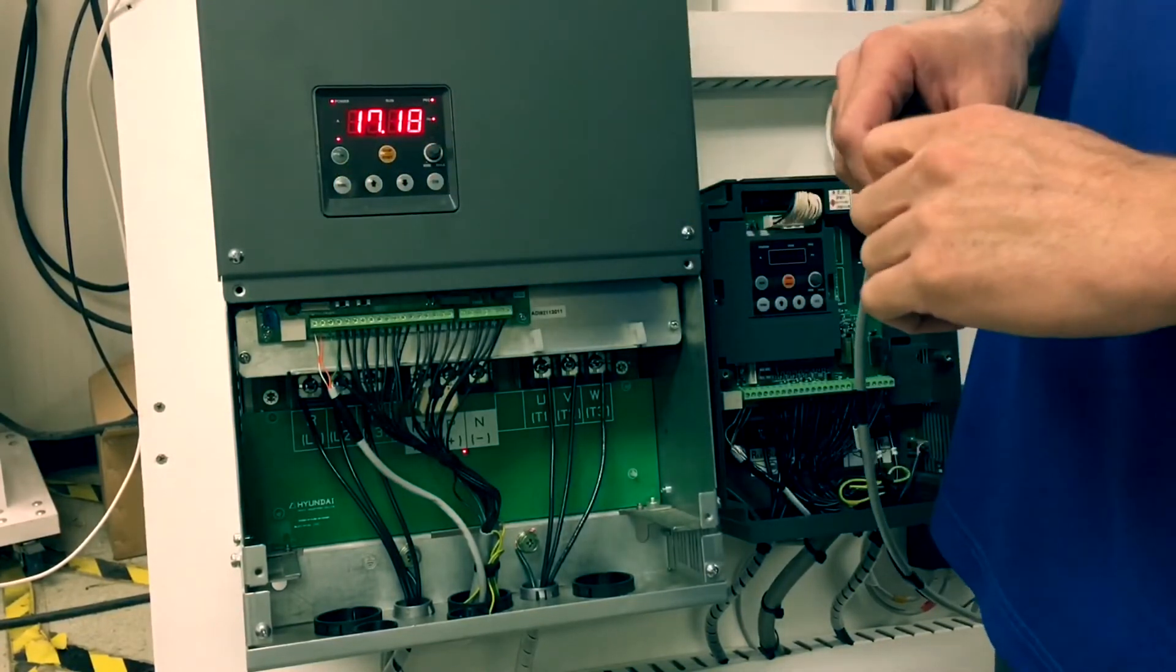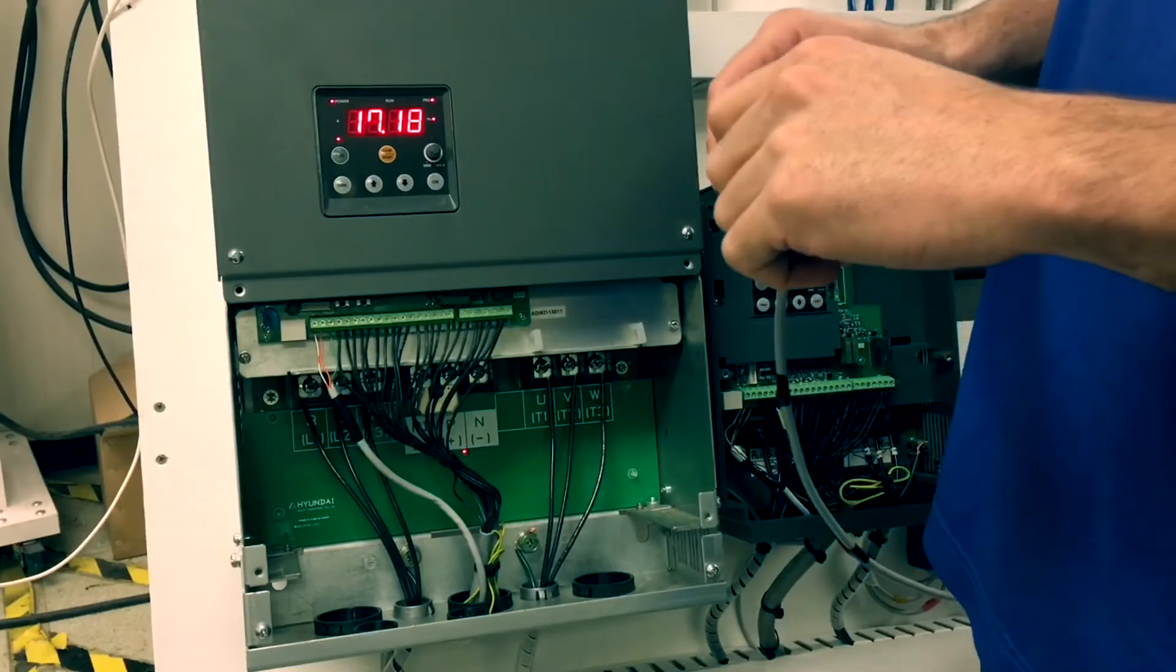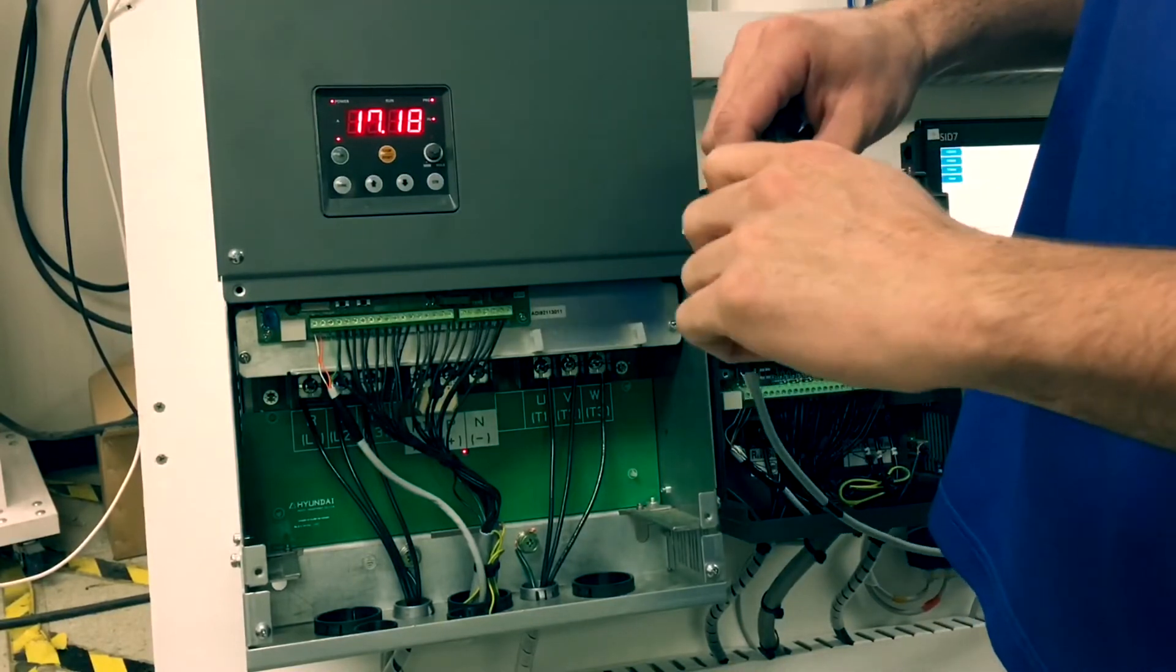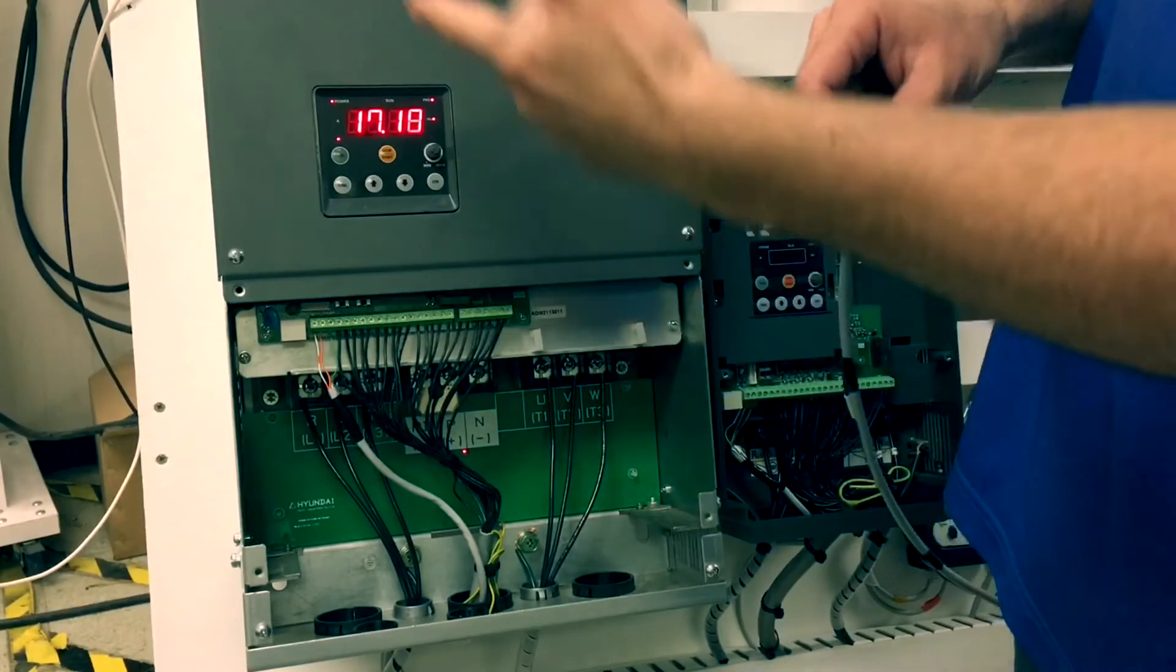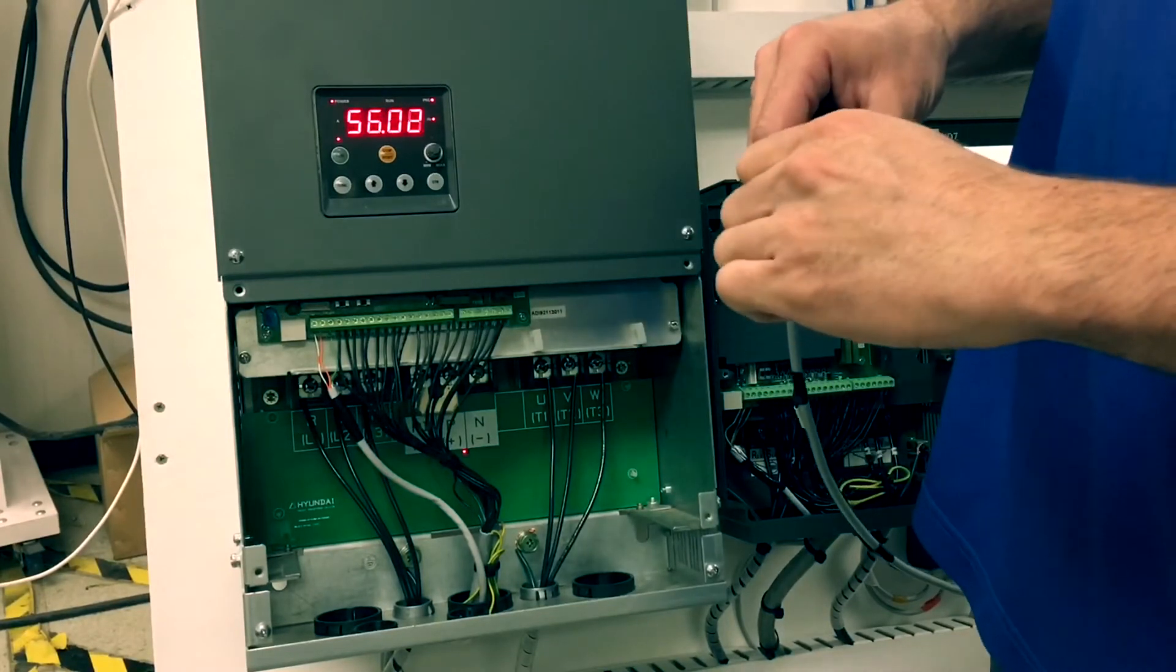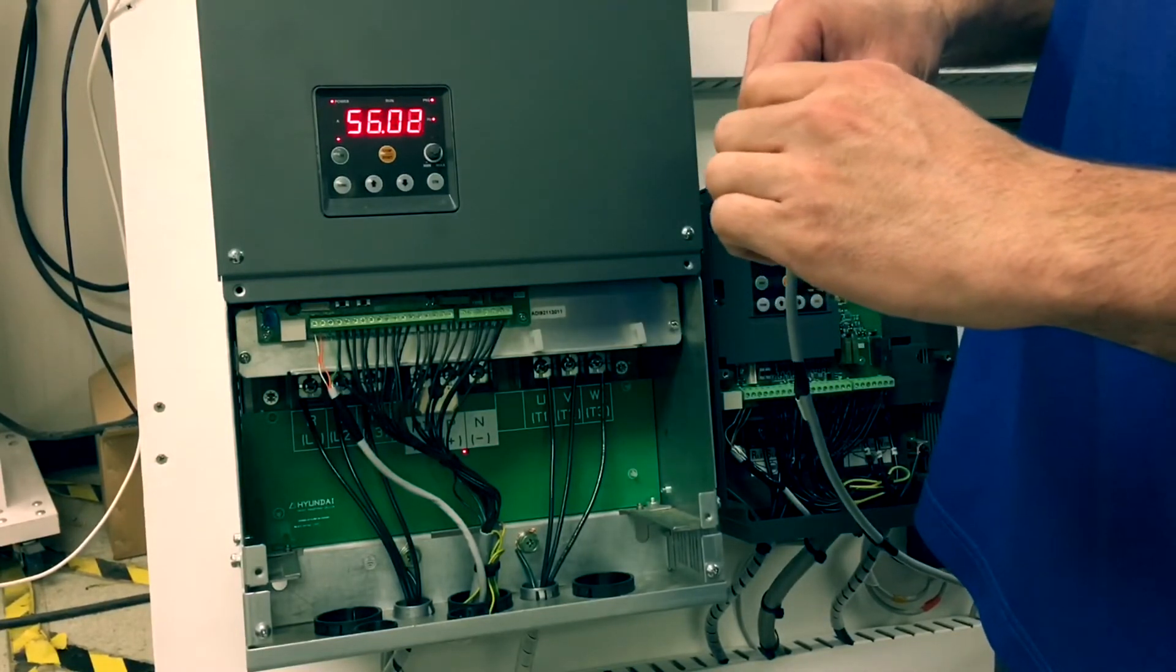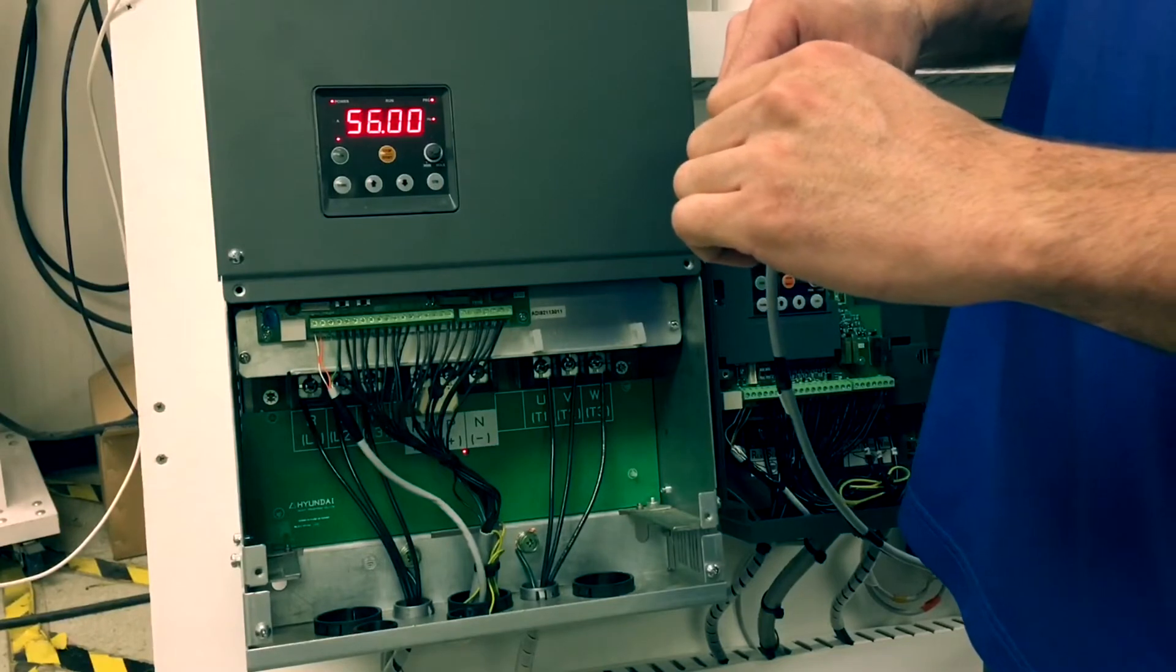You will see 0 volts on the potentiometer will read 17 hertz, and at 10 volts on the speed potentiometer you will roughly see 56 hertz. We need this to show 0 to 60 hertz.